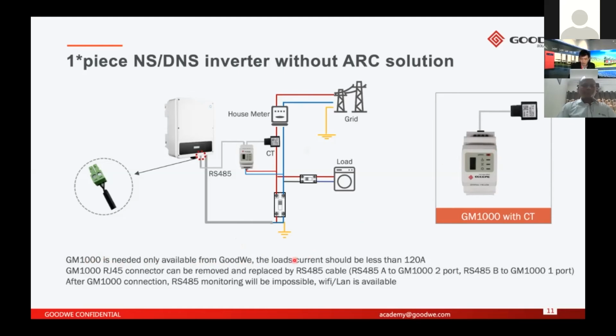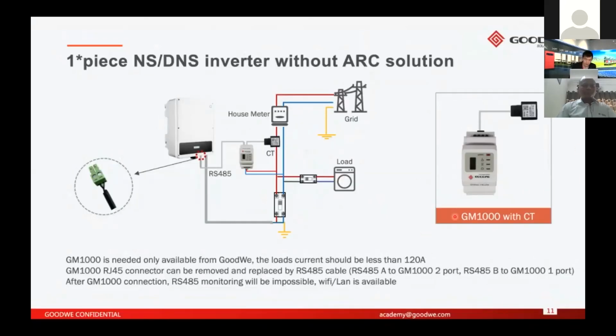And the load current should be less than 120 amps. Because of the CT, you can find the CT connected to the main cable of the house, just behind the house meter. So the CT will measure all the power, including the loads' consumption. So if the loads' consumption is less than 120 amps, it's fine. But if the loads' consumption is higher than 120 amps, there is another solution that I will introduce. You can't use the GM1000 to do it.